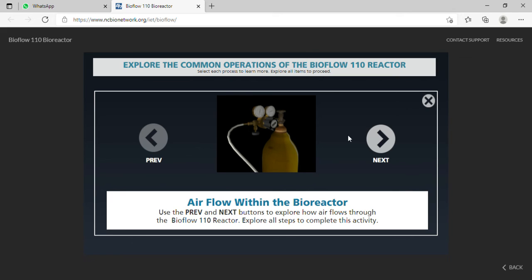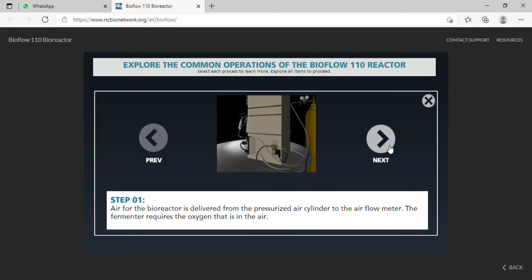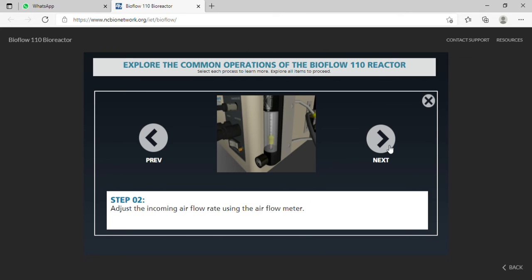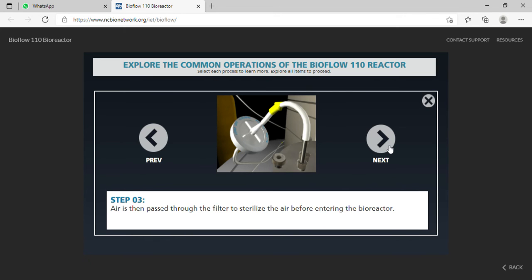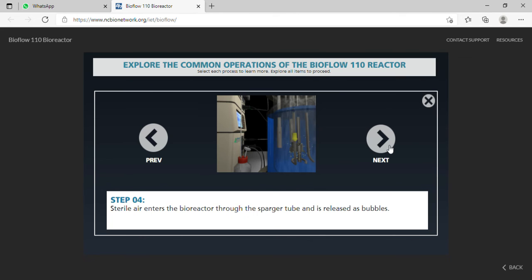Process 4 is airflow within the bioreactor. Step 1. Air for the bioreactor is delivered from the pressurized air cylinder to the airflow meter. The fermenter requires the oxygen that is in the air. Step 2. Adjust the incoming airflow rate using the airflow meter. Step 3. Air is then passed through the filter to sterilize the air before entering the bioreactor.